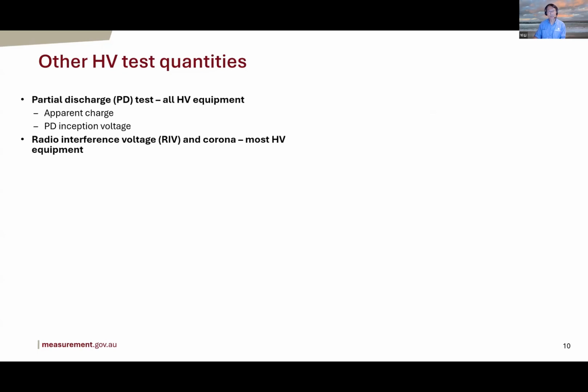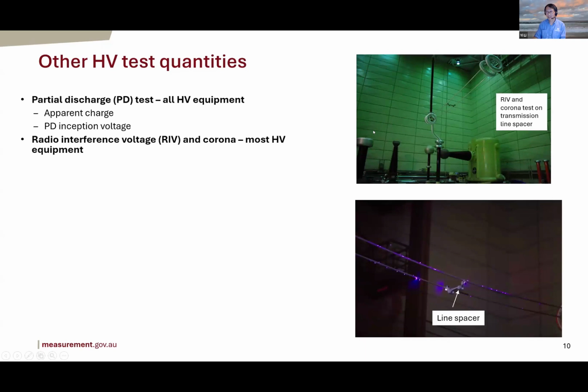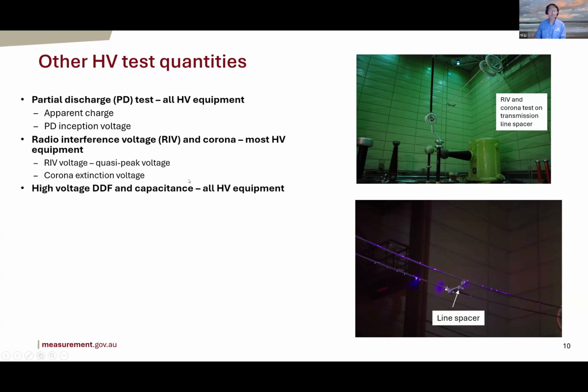Another quantity or test is the radio interference or corona. The corona is the external discharge on high voltage terminals, or high voltage conductors. So in a transmission line, you have, say, some fittings like the line spacers. On the high voltage, they will discharge. And this discharge creates radio frequency, high frequency interference to the communication networks and radio broadcasting networks. So these need to be kept below a certain level. And that's why all these line fittings and many other equipment need to be tested for this quantity.